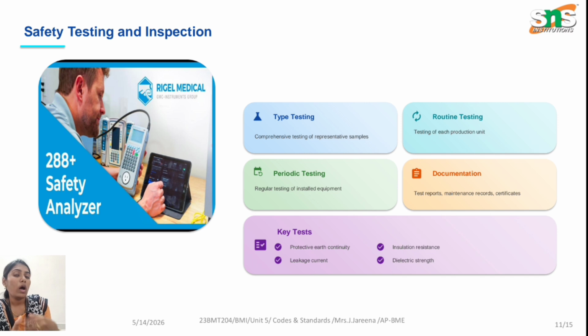How can we check? Through safety testing and inspection. We have to test earth leakage current, ground testing, and so on. We have to make this testing routine, that is called routine testing. We can also make it periodic testing, like once a month or once in 2 months. For each and every test, we have to make documentation to recall issues in the future. The key tests are the continuity test, leakage current test, insulation test, and dielectric strength test.